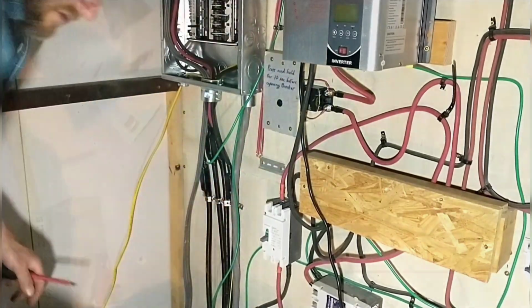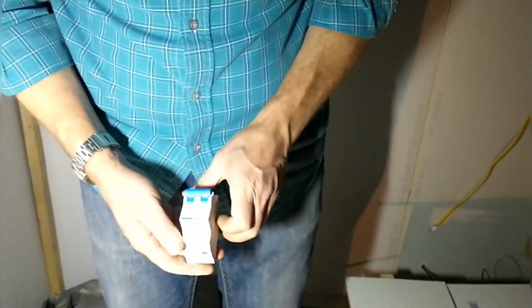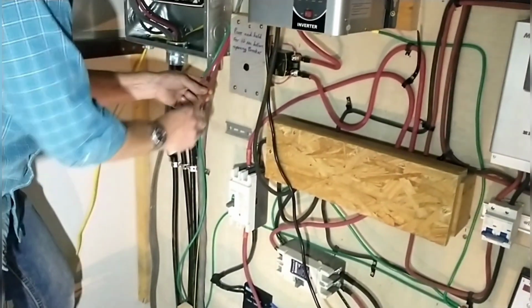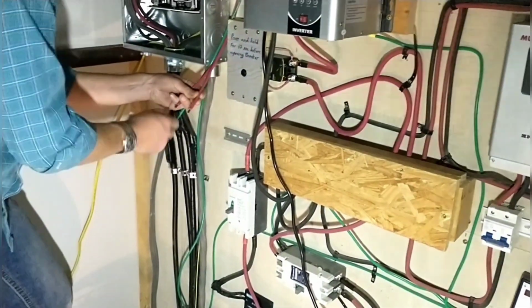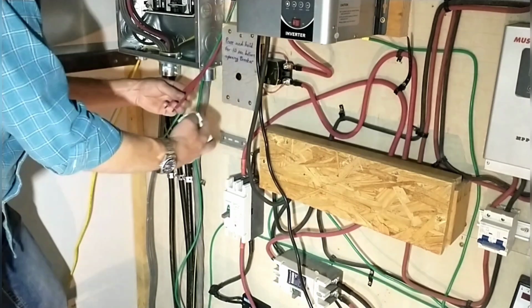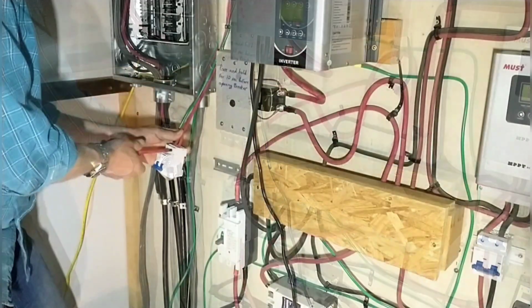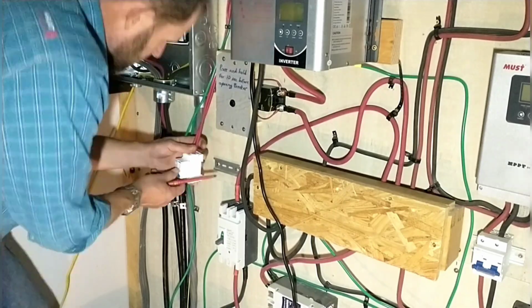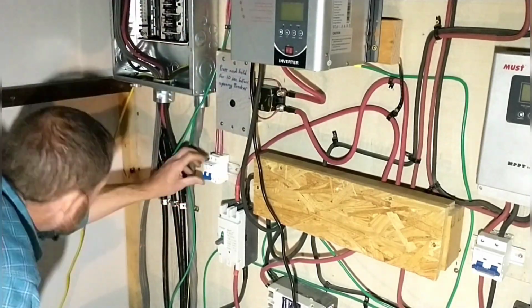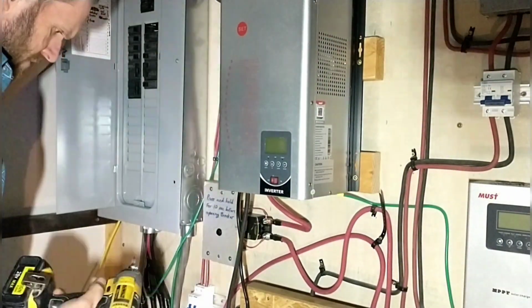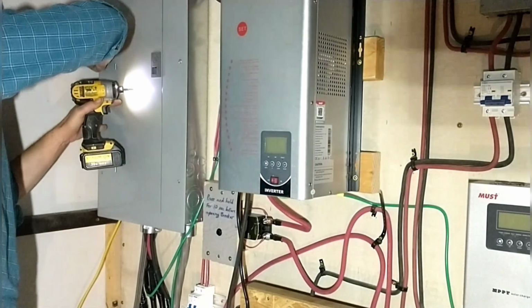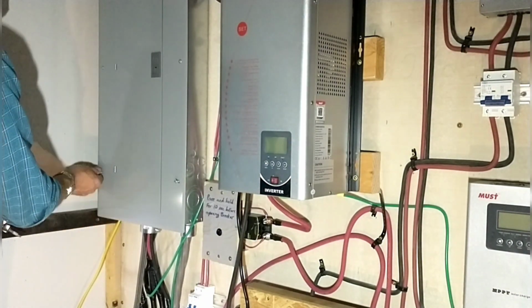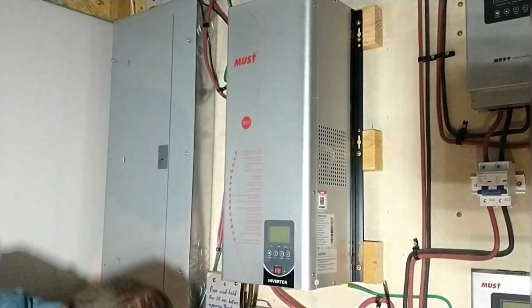Once that was complete, I was ready to move on to my last task before re-energizing the system: getting ready to connect generator power. Our inverter has the ability to take power in from a generator, convert it to DC, and recharge the batteries. To do that, I need to connect the wiring and have an AC breaker for 220 volts, and get all that wiring done so that in the future, if I want to use the generator to power up the batteries, I can. Fortunately, it's not something we've needed in the past, but it'd be nice to have the option in the future.